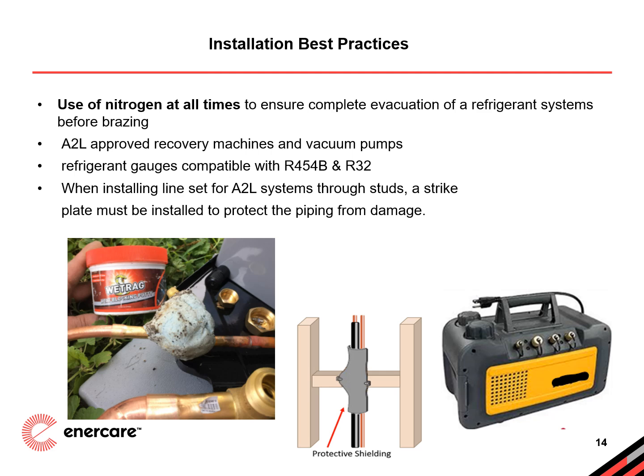Proper installation of refrigerant piping is critical for the performance and safety of A2L systems. Follow our best practices in the Operations Manual, Section 8, to ensure secure, leak-free joints. Use nitrogen before, during, and post-brazing to purge the lines, prevent oxidation, and ensure all joints are properly inspected after cooling. Keeping rotolock, service valves, and the internal components cool by applying a drenched cloth or wet rag putty continues to be an important practice, and maybe more with the change to A2L refrigerants and equipment. Tech Services is also in the process of testing and pursuing the use of a reliable, no-braze fitting option to limit the amount of hot work. More information to come as that testing progresses.